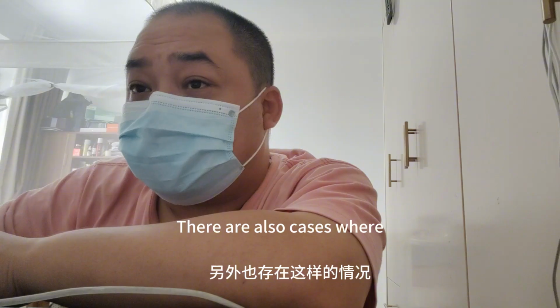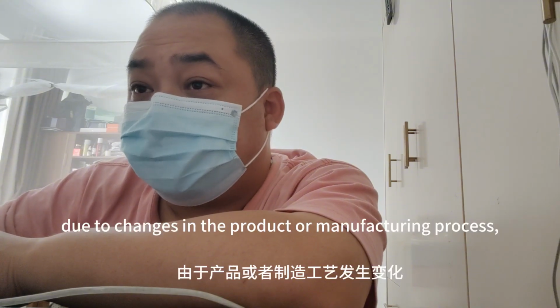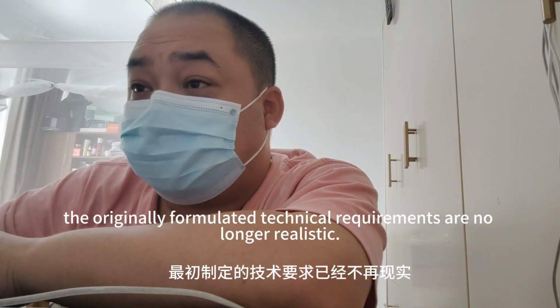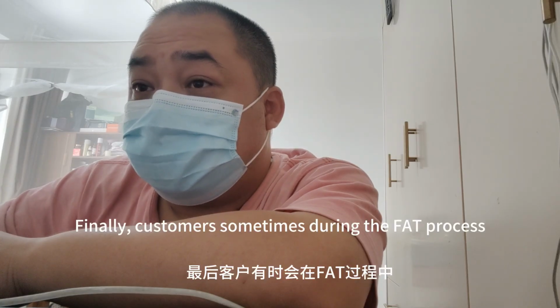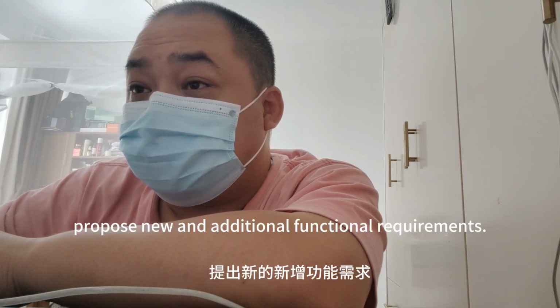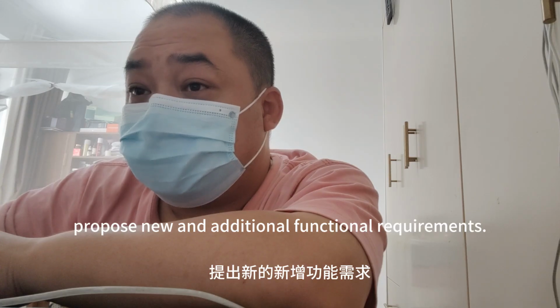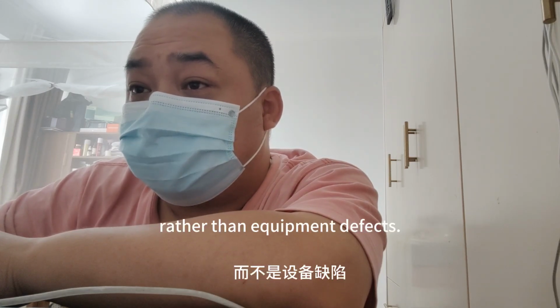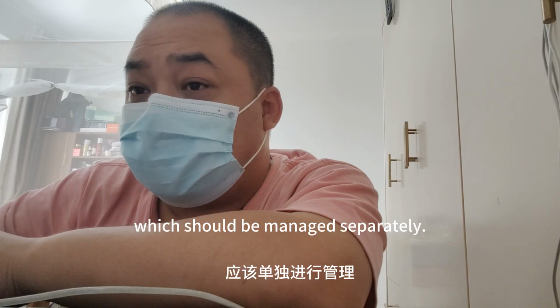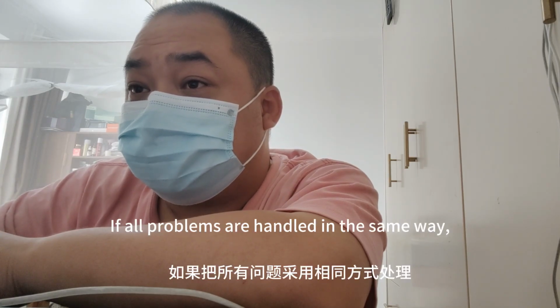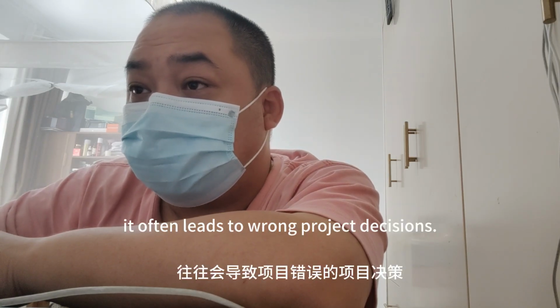There are also cases where, due to changes in the product or manufacturing process, the originally formulated technical requirements are no longer realistic. Customers sometimes propose new and additional functional requirements during the FAT, which is a project change rather than an equipment defect, and should be managed separately. If all problems are handled in the same way, it often leads to wrong project decisions.